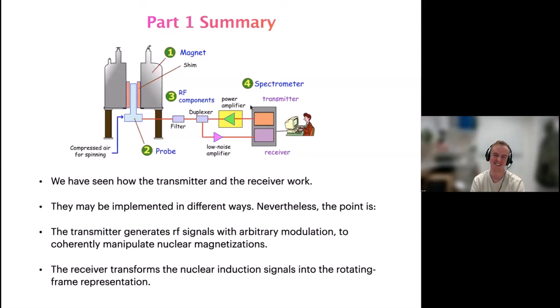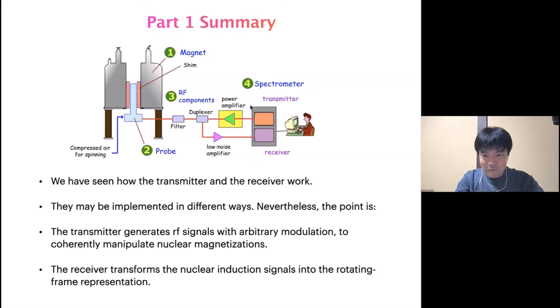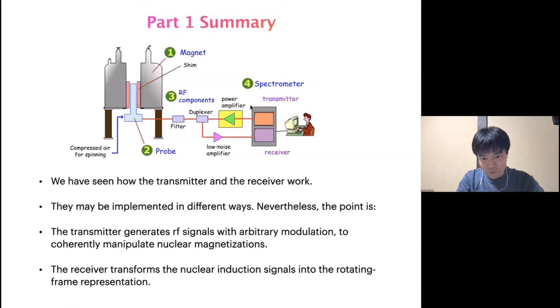Another question: what do you do about temperature drifting on your spectrometers, since temperature variation makes the FID frequency change? Is the 1 Tesla spectrometer stabilized for temperature? For the 1 Tesla permanent magnet, the magnetic field drifts if the temperature changes. For the superconducting magnets, it doesn't matter at all — the frequency of the spectrometer is stable enough.